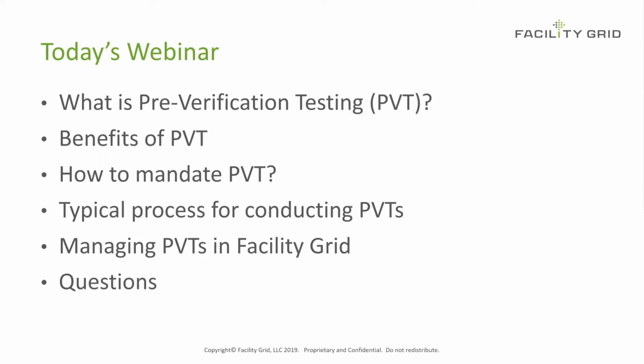Contractors should be encouraged to submit any questions or suggestions if they're not able to perform certain tests as described in a script, or if they believe there is a better way for conducting them. This can be done by generating issues directly from the pre-verification tests and assigning them to the commissioning agent or to the engineer of record. This could also be done by submitting an RFI through the typical RFI submission process. Also, snapshots of trends can be attached to the pre-verification tests for review with the engineer of record and the commissioning agent if the contractors are unable to achieve the expected results.